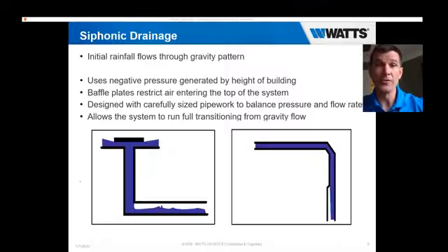What occurs is as rainfall increases and the ponding level increases on the roof, adding more weight to the structure, the siphonic system, at a lower water level than gravity, closes off all of the air, which allows the piping to prime itself, push out all of the air pockets in the pipe itself and create a suction effect. So this is drawing the water from the roof.